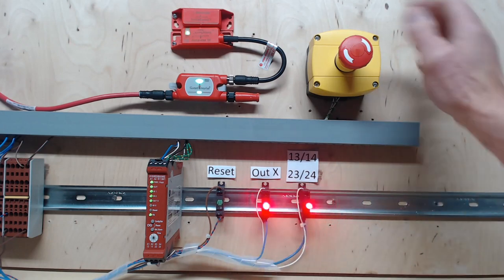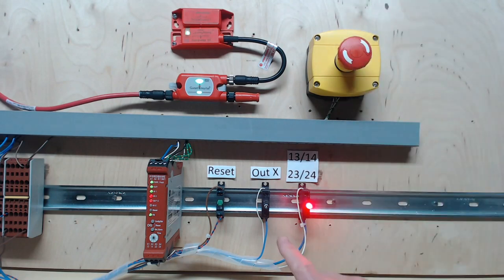Now if you press the E-stop or open up the gate, you observe that the out X output turns off immediately and the safety outputs have a three second delay.